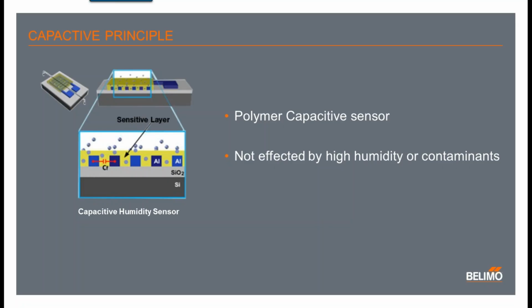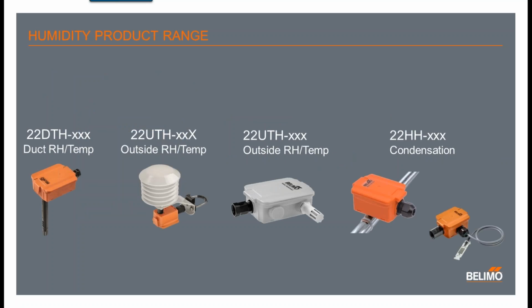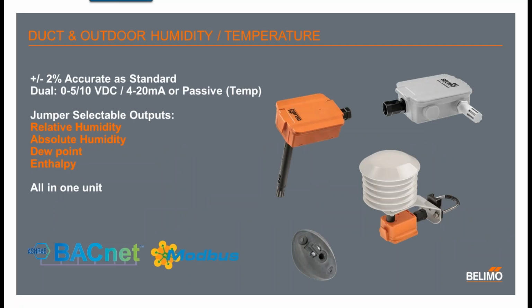Our humidity sensors. The sensing element is the polymer capacitive sensor, which means it is not affected by high humidity or contaminants. Our humidity range includes combined duct humidity and temperature sensors, outdoor humidity and temperature, and also condensation sensors. All of our humidity sensors have plus or minus 2% accuracy as standard across the whole range.